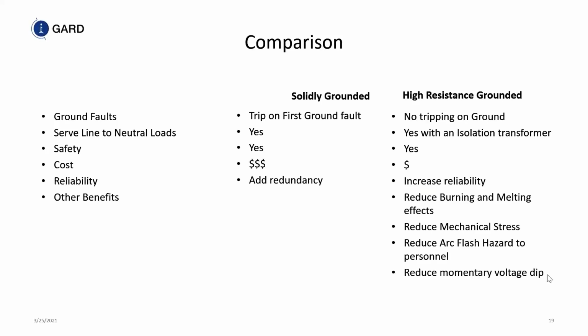Reduce momentary voltage dip. You've seen when you've had a ground fault or you start a large motor, the voltage dips to some degree and something can happen after that. With resistance grounding, you're not going to get that as much because you don't have such a strain on the primary due to the inrush of current on the secondary.